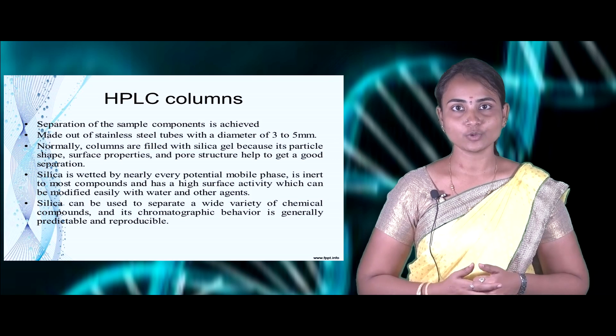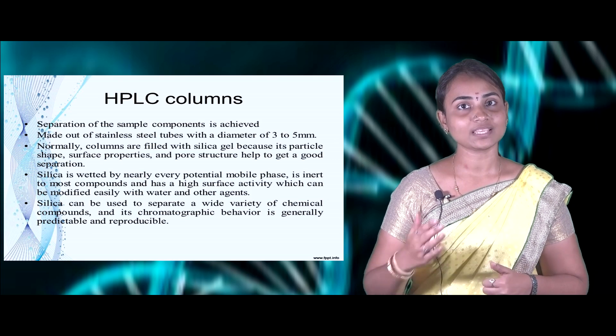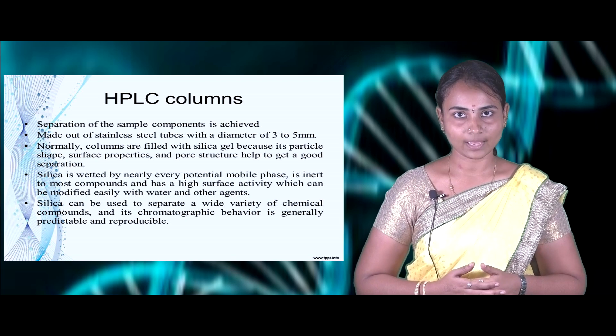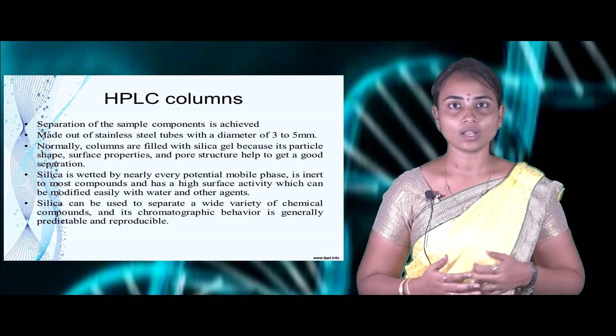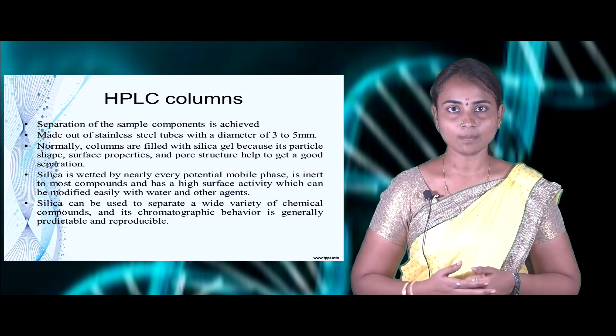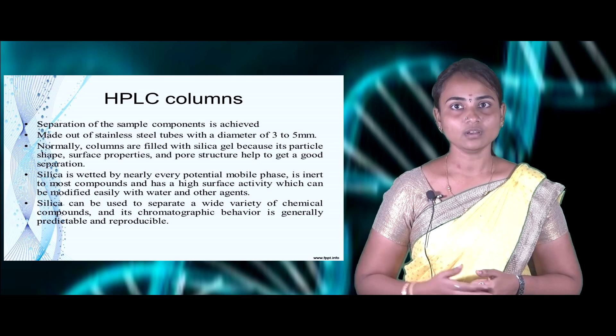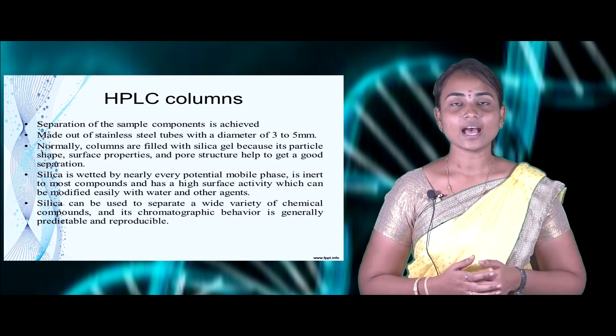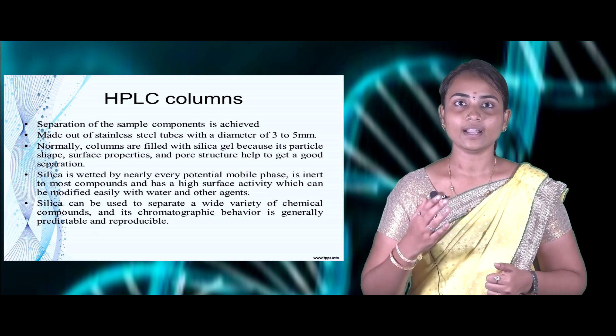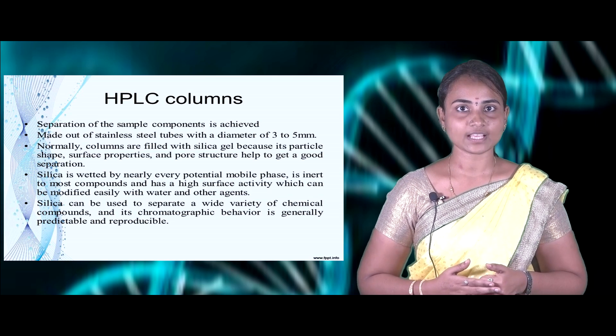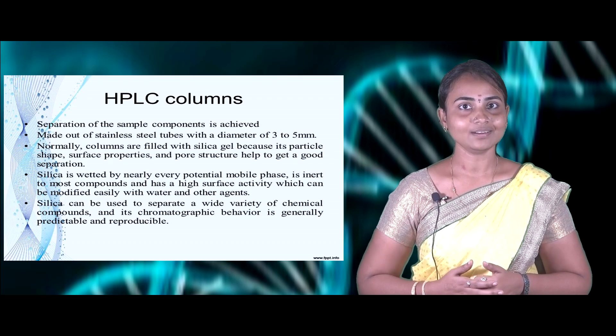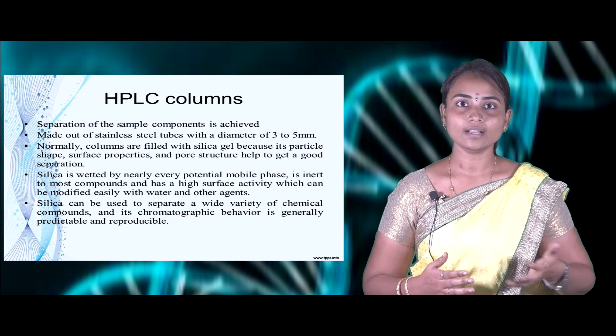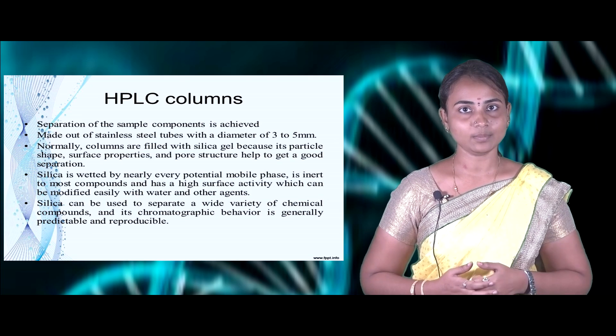Coming to the HPLC column: it is used for highly sensitive separation of different components based on their partition behavior. It is made up of stainless steel tubes with a diameter of 3 to 5 mm and is normally filled with silica gel, because silica gel's particle shape, surface properties, and pore structure help determine the quality of different analyses. As silica gel is used as a stationary phase, it is highly compatible with nearly every composition of solvents, and being highly inert with high surface activity, it can separate different components based on their polarity. Silica gel can separate a wide variety of chemical compounds, making the chromatography highly predictable and reproducible.